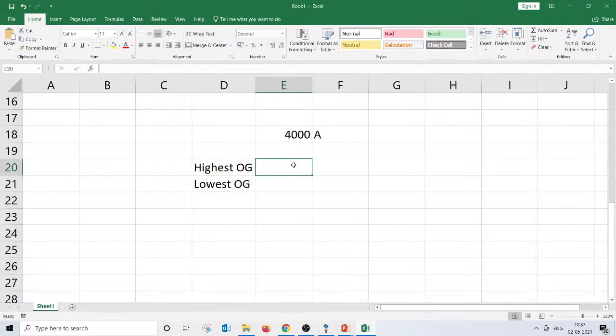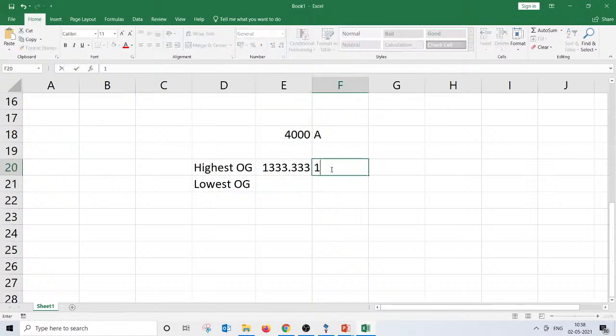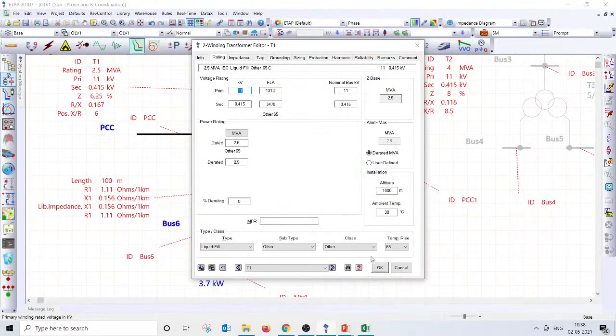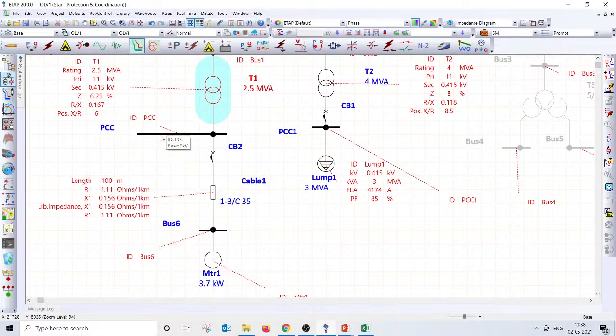So the highest outgoing should not be more than about one third. What I mean by that: if you divide this by 3, you will get 1300 amps. Then you cannot really go beyond 1200 amps as a single outgoing feeder from this LV switchgear, this PCC. If you do, you are not using this PCC effectively. If one single load is more than 1250 amps, then instead of moving this PCC, you can probably move that to that place itself.